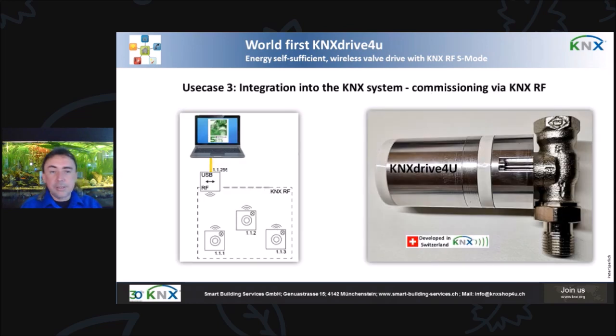How to do it? You use a laptop with the ETS, then you use one of these sticks. It's a KNX RF programming stick, and then you can go through the air on RF directly to the devices, as you would now, maybe if you use ETS5. So you know how to do it with the twisted pair devices, and now you just do the same with the KNX RF.